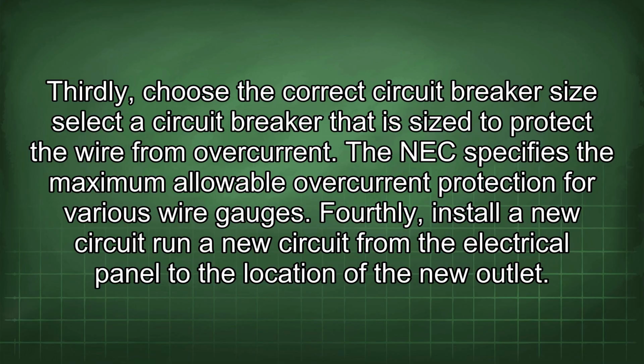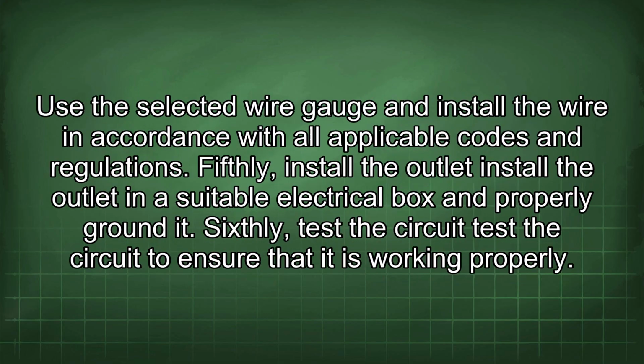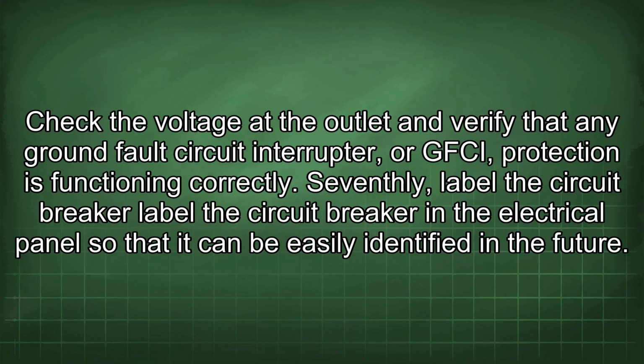Fourthly, install a new circuit. Run a new circuit from the electrical panel to the location of the new outlet. Use the selected wire gauge and install the wire in accordance with all applicable codes and regulations. Fifthly, install the outlet. Install the outlet in a suitable electrical box and properly ground it. Sixthly, test the circuit. Test the circuit to ensure that it is working properly. Check the voltage at the outlet and verify that any ground fault circuit interrupter, or GFCI, protection is functioning correctly. Seventhly, label the circuit breaker. Label the circuit breaker in the electrical panel so that it can be easily identified in the future.